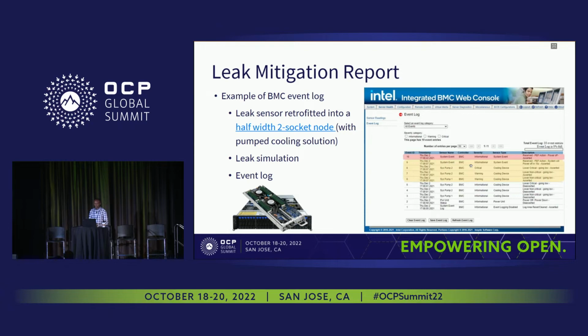Right. And then this is an example of what the event log looks like if you want to go back and troubleshoot when the leak occurred and how it occurred, which location and all that. If you have a multiple leak detection system for redundancy, which is recommended, if one sensor goes bad, you have to make sure that you have a redundant system. That way, you protect the equipment better.